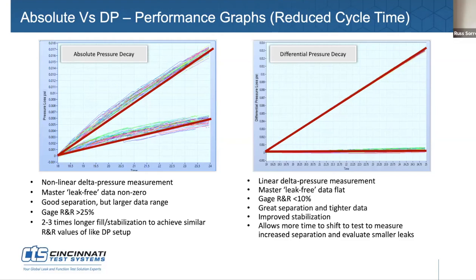So what are some ideal applications for differential pressure decay, just to give some perspective to the customer? Some really good ones: higher pressures, higher than 50 psi. That way you've got this thermal event that nulls itself out. Really low leak rates, small parts with low leak rates. Differential can test very well on those. Those are a couple of the really good ones to look at.